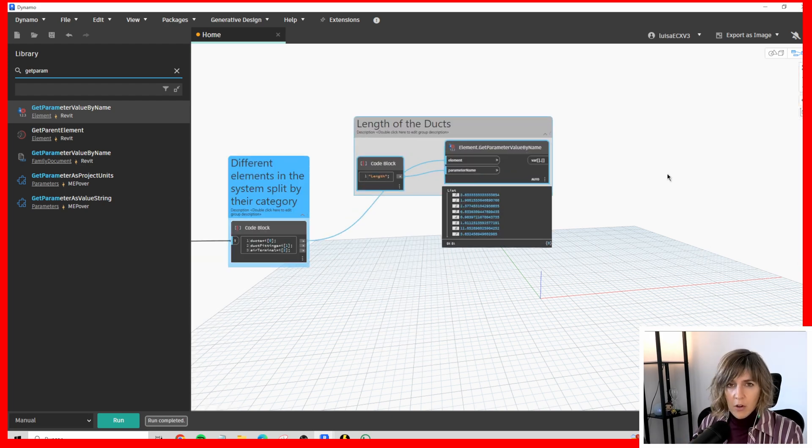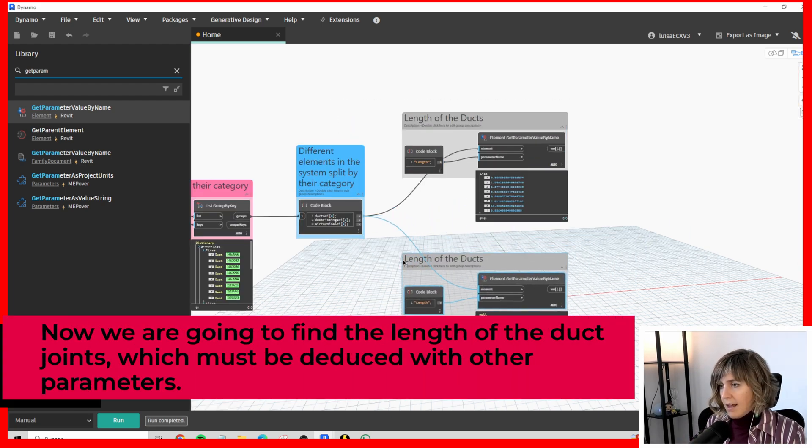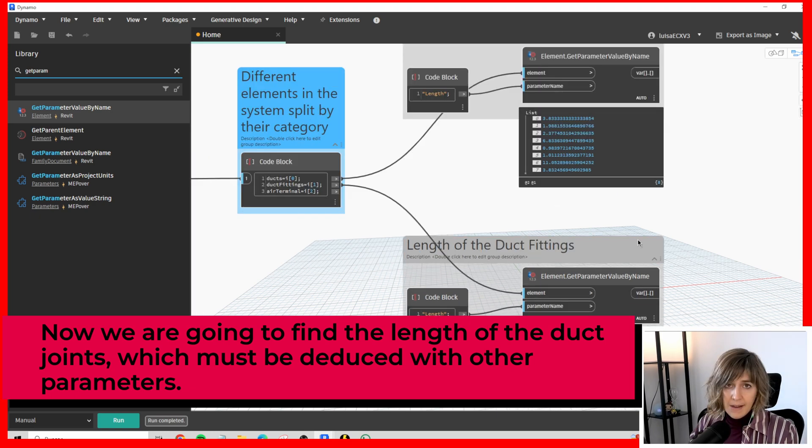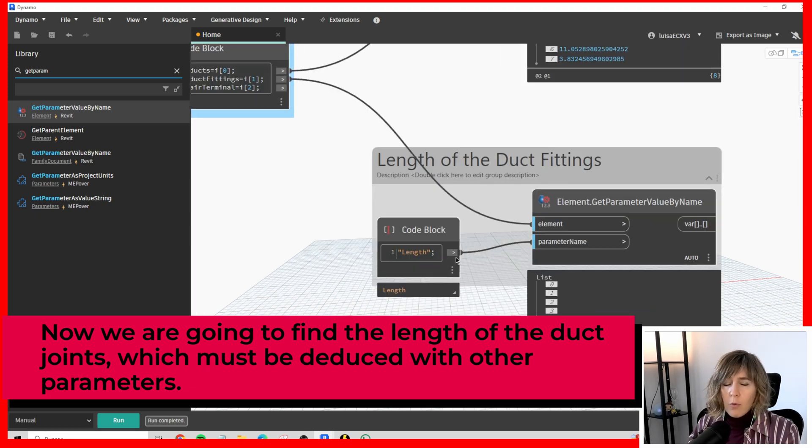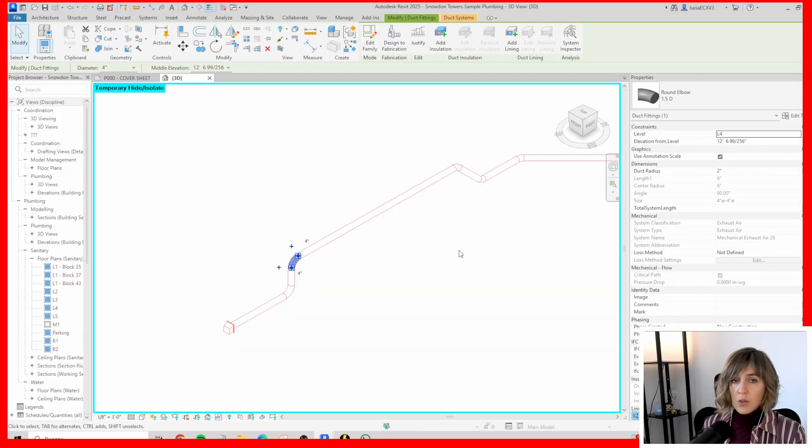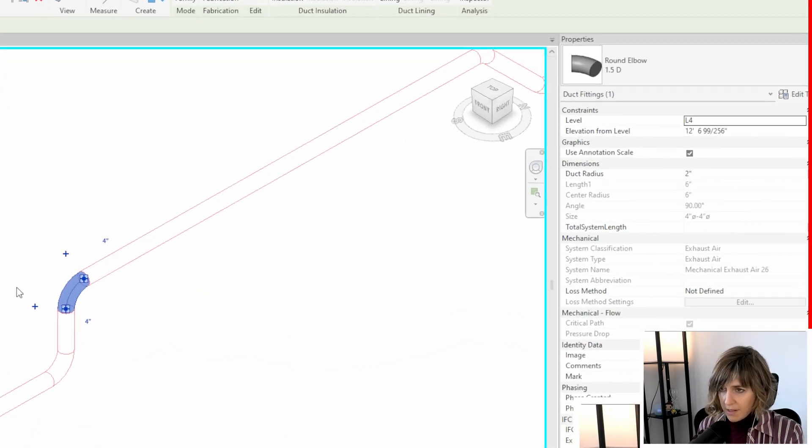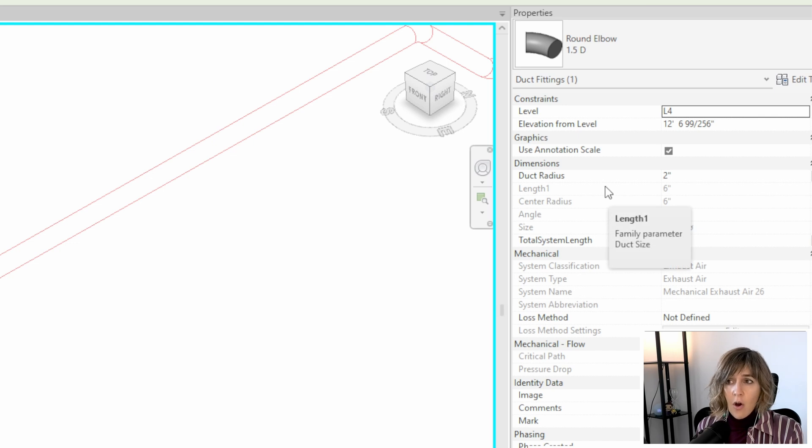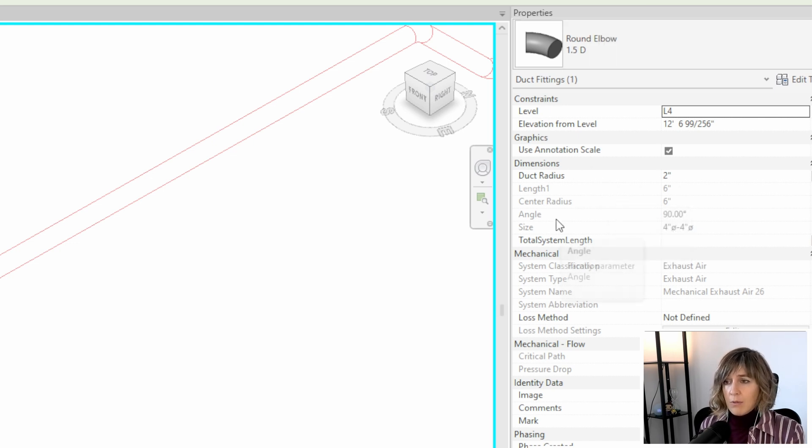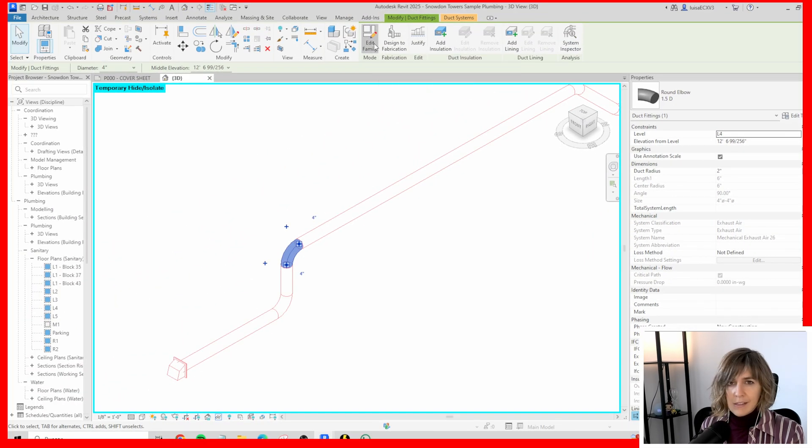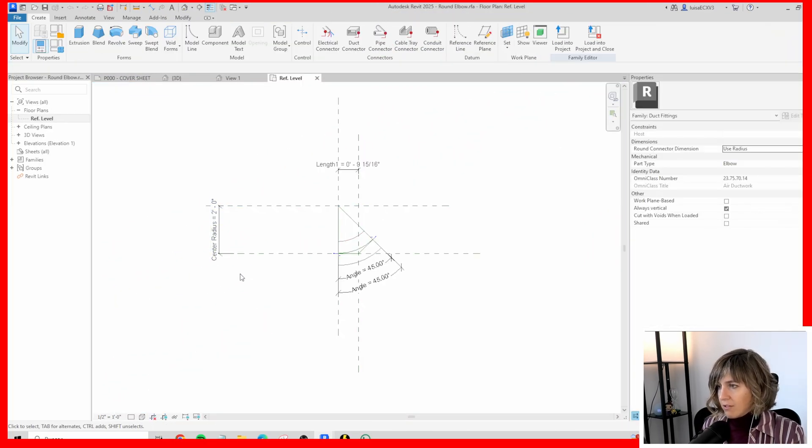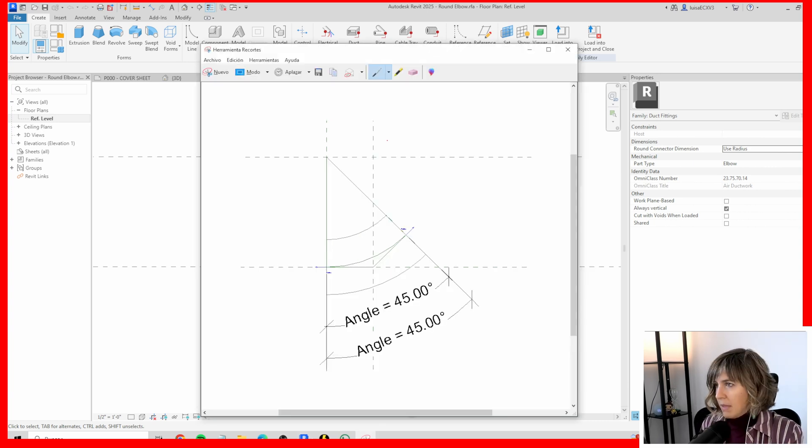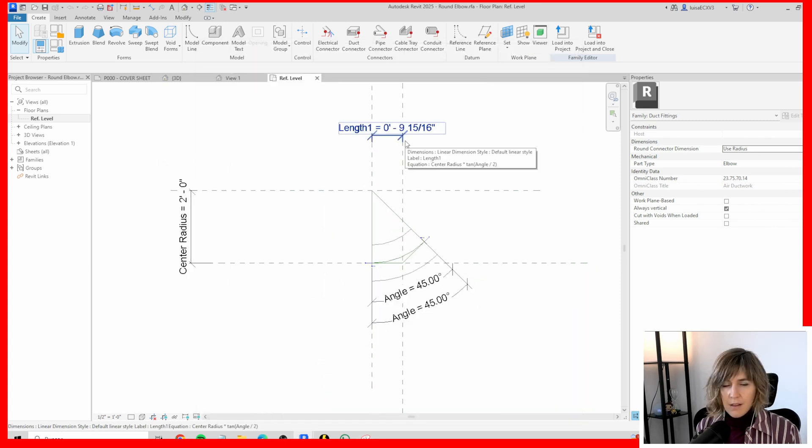We have here the length of the ducts and here we have the different elements separated by their category. If I copy this and if instead of ducts, I select the duct fittings and I run this, as you can see, everything is blank. Why is that? Because the duct fittings do not have the length in the length parameter. So, we head to Revit and check the different parameters of these duct fittings. In this case, we have the round elbow and we have the angle, the center radius, size.